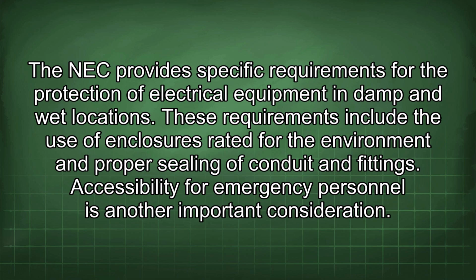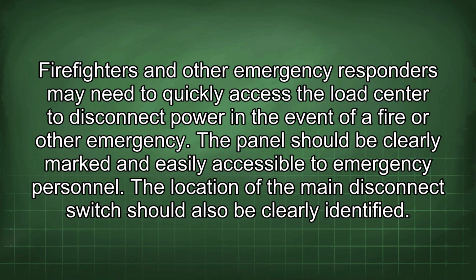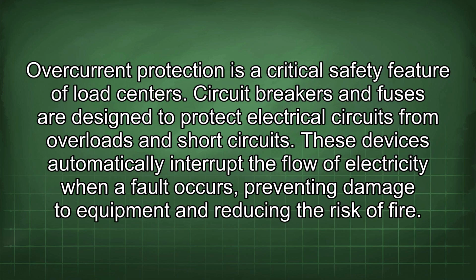Accessibility for emergency personnel is another important consideration. Firefighters and other emergency responders may need to quickly access the load center to disconnect power in the event of a fire or other emergency. The panel should be clearly marked and easily accessible to emergency personnel. The location of the main disconnect switch should also be clearly identified. Overcurrent protection is a critical safety feature of load centers. Circuit breakers and fuses are designed to protect electrical circuits from overloads and short circuits. These devices automatically interrupt the flow of electricity when a fault occurs, preventing damage to equipment and reducing the risk of fire.